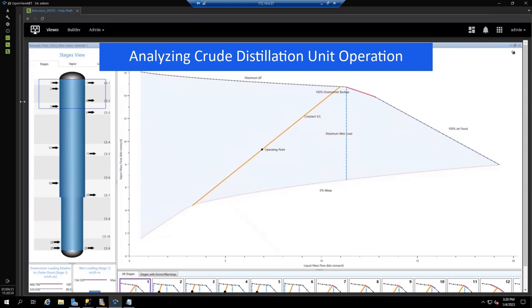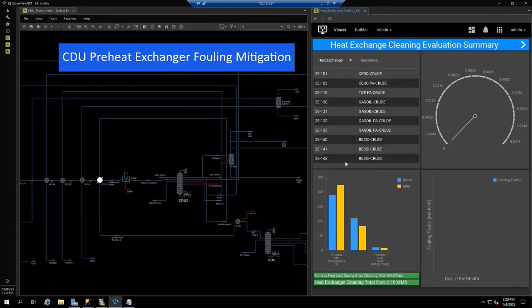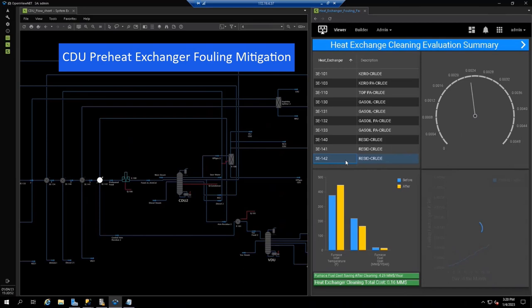A unique and powerful visual display shows the internal performance of the column. It's easily readable by others in operations. In this case, we quickly see that hydraulic profiles are within the recommended operating envelope, so that is not the cause of the emissions delta. Turning to a more detailed flow sheet, we see a heat exchanger is flashing, leading the technical team to check the fouling rate in this unit.